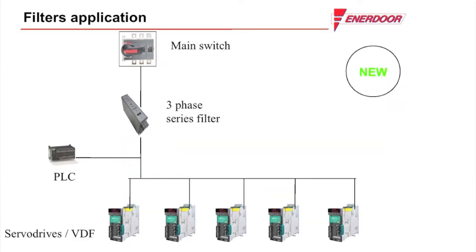This demonstration represents a multiple AC drive installation, with a single filter located after the main switch. This configuration reduces cost and protects the entire machine from the noise generated by the drives, as well as the noise that could be coming from the main line of the facility.